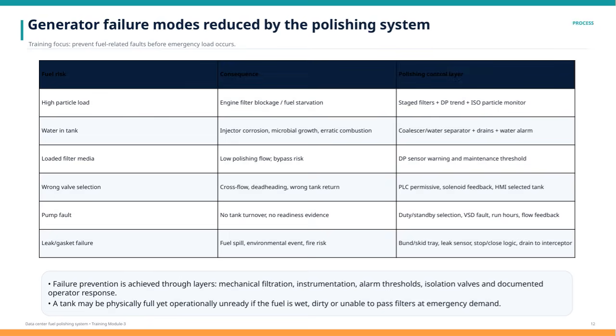If there's water in the tank, it can lead to injector corrosion and erratic combustion. We address this by using coalescers or water separators, regular draining, and water alarms. Loaded filter media can reduce polishing flow and risk bypassing filters, so we rely on differential pressure sensors with warning and maintenance thresholds. Wrong valve selection can cause fuel to flow incorrectly or return to the wrong tank, which we control with programmable logic controllers, solenoid feedback, and monitoring on the human-machine interface.